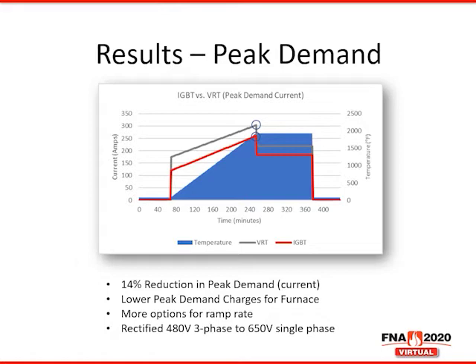And the reason why we see a lower peak demand is that our control, which I'll get into later, we rectify the three-phase 480 volts upstream to 650 volts out of the control into the transformer. That higher starting voltage allows us to step down that voltage further in the transformer, and that results in a lower primary current draw, which you see throughout the entire system.